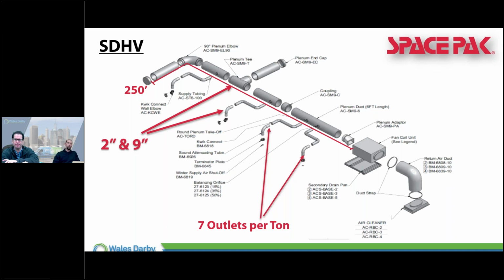So now we go and do an equipment swap, and we still have maybe some old 7-inch duct, the way it used to be. And now we're putting this new machine on, we're on smaller ducts with higher airflow. You should kind of get where I'm going with this. You're going to have some noises, you're going to have some unhappy customers. And that's where, unfortunately, we end up having to step in sometimes.